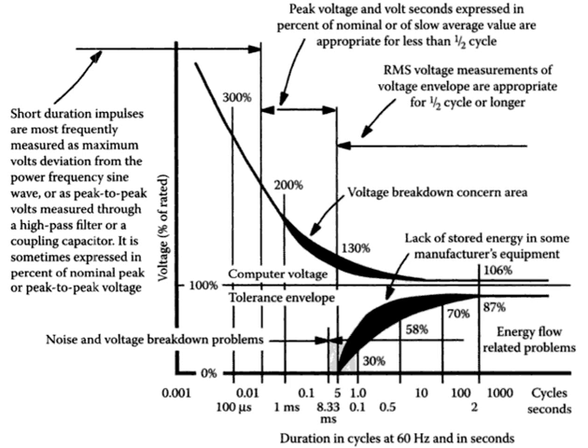The term brownout is an apt description for voltage drops somewhere between full power, bright lights, and a blackout, no power, no light. It comes from the noticeable to significant dimming of regular incandescent lights, during system faults or overloading, etc., when insufficient power is available to achieve full brightness in, usually, domestic lighting. This term is in common usage, has no formal definition, but is commonly used to describe a reduction in system voltage by the utility or system operator to decrease demand or to increase system operating margins. Overvoltage occurs when the nominal voltage rises above 110% for more than 1 minute.